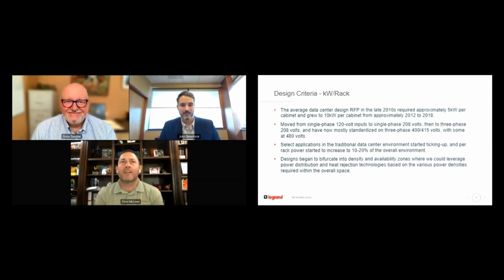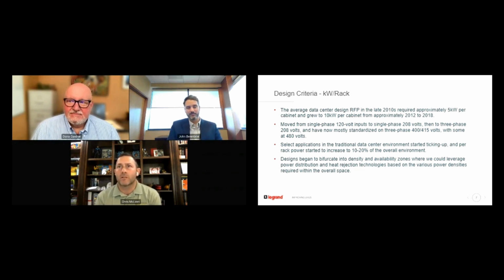As a design engineer and former data center operator, the most common request from a power density standpoint, from an electrical receptacle standpoint, was an L630 for many years, 3 to 8 years probably. That went from 20% of your environment to 50 to 80 to 100%, and then it started backing down again. And what you're talking about is a 5 kW rack effectively, just like you said, John. The average utilization of the 5 kW rack was typically 3.6 kW.